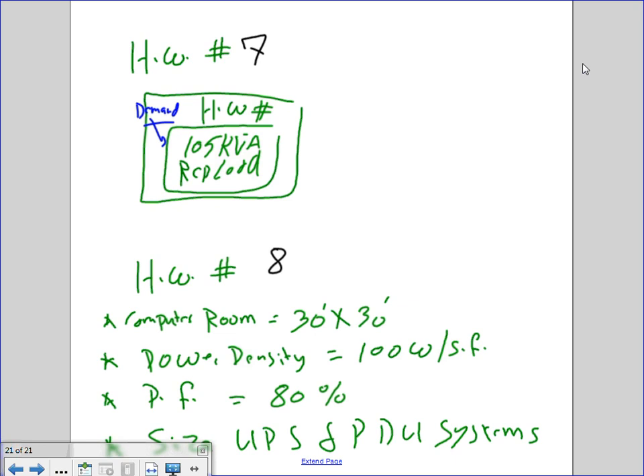Okay, this is similar to the receptacle second example. This one here is a computer room, 30 by 30, power density 100 watts. I need this one to be changed, guys, to 90% power factor. 90% power factor, and size UPS and PDUs. Do we have a loss factor? We don't have a loss factor. So let's do a loss factor of 10%. Can you please add this one? Loss factor is 10%. So this is like the first example that we did about the PDU.